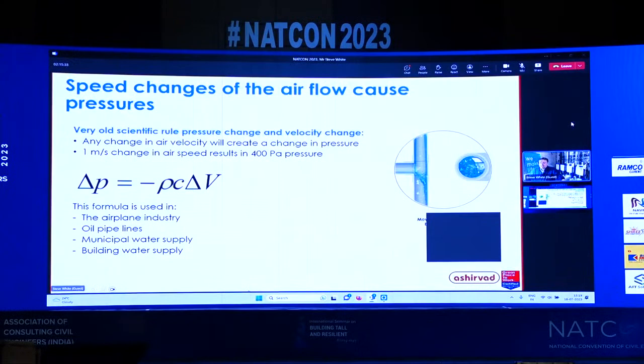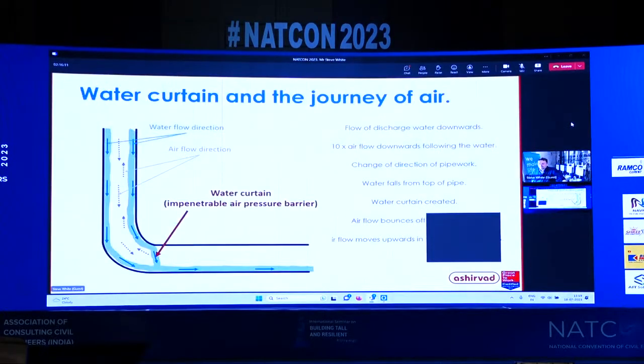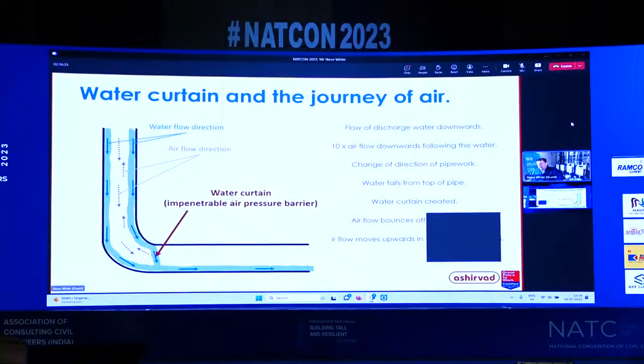And the way we look at that is the speed of change, or the rate of change, from the oil industry, water supply, building water supply, but also in drainage. With oil pipes and water supply, they're a high frequency pressure wave. Within a drainage system, they are a low amplitude pressure wave, so more like a long wave radio length. So our wavelengths are different, but the principles of fluid mechanics, pressure transfer, are exactly the same as other fluid systems. But when we interrupt the airflow, we cause a rate of change, and we're talking a rate of change in 10 milliseconds. So it's a very, very fast rate of change just by the water curtain changing direction and causing a barrier and back reflection coming up the drainage system.